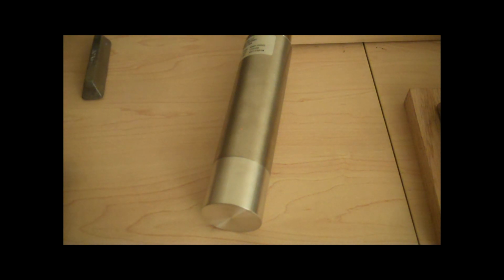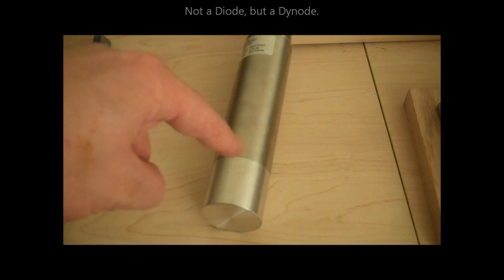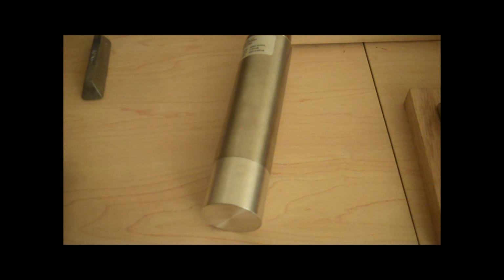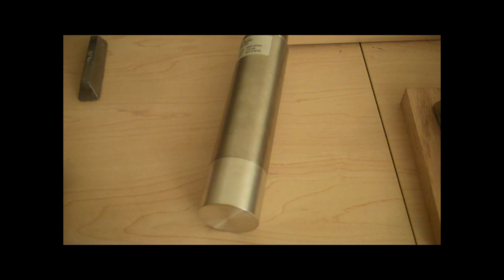The ultraviolet light immediately hits a photocathode. As the ultraviolet light strikes, the photocathode emits electrons. The pulse of electrons that it emits are immediately directed against a dynode. The dynode, when struck with electrons, emits even more electrons, a specific number of them. These electrons move up a chain of more dynodes, gaining more and more electrons at discrete levels, until they strike the very back of the unit, where they're picked up by an anode and registered as a pulse which goes to the machine. As a result of this, the scintillation counter is not only incredibly sensitive, but also capable of detecting energy.